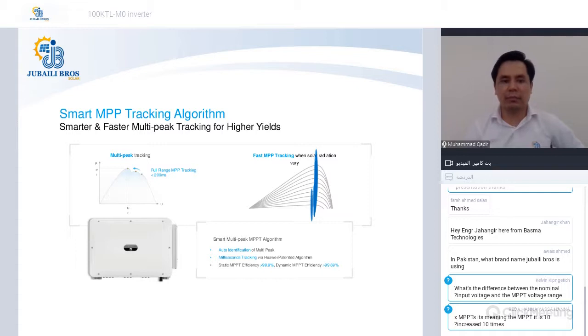Huawei uses a smart MPP tracking algorithm. This is auto detection and happens in milliseconds. And Huawei MPPT efficiency, static efficiency is 99.9% in this inverter, and the dynamic efficiency is 99.69%, which is at the higher end compared to other inverter manufacturers in the market. The multi-peak scanning of MPPT results in this higher efficiency of the inverter.